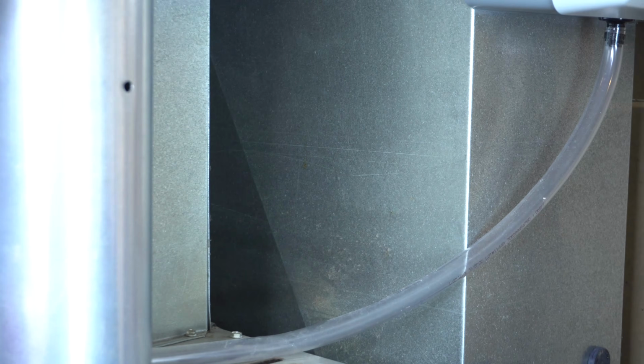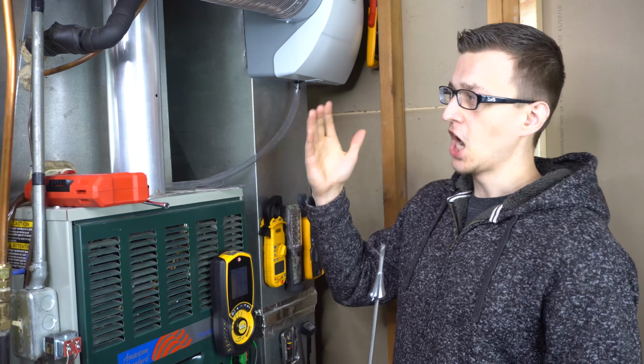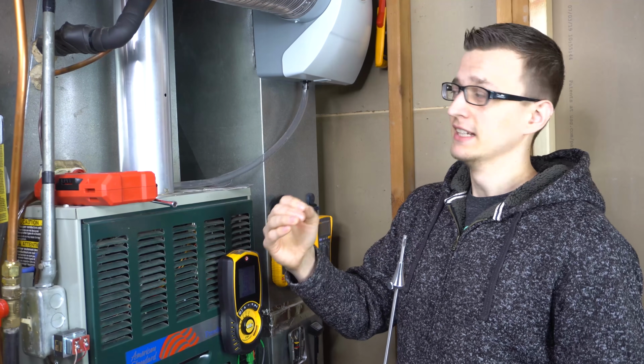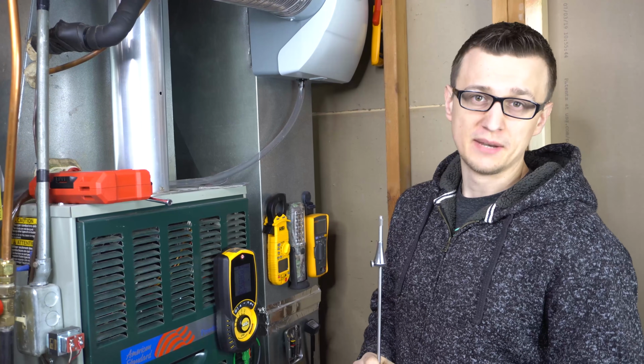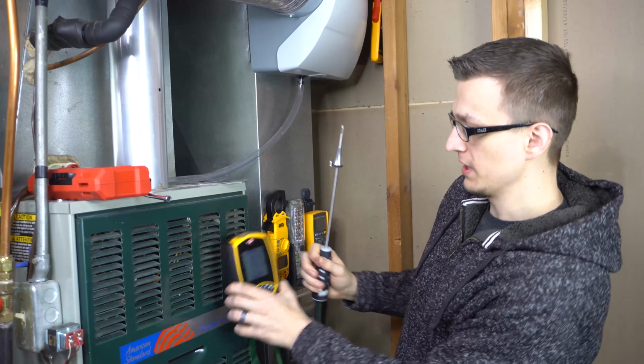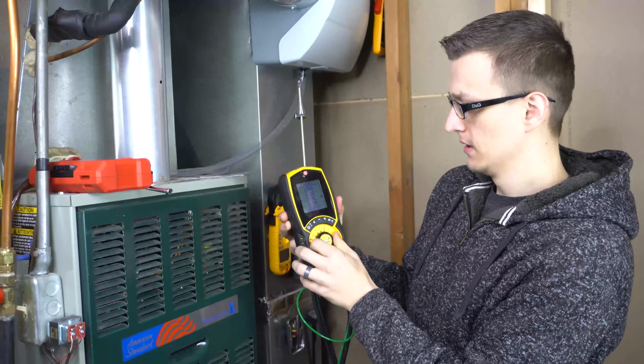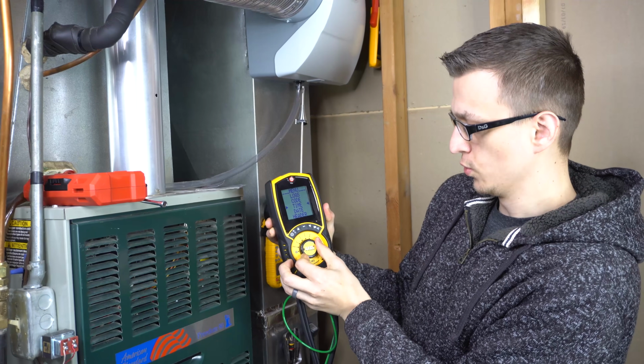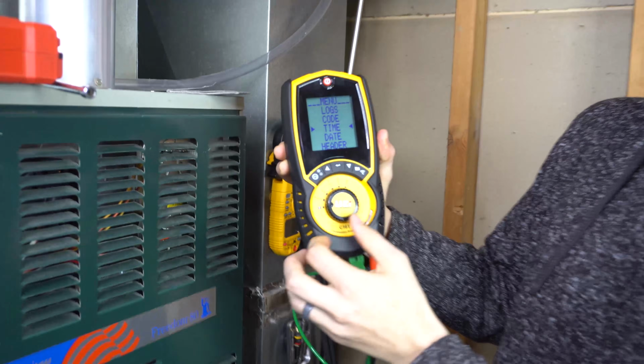So anyways, we have our hole drilled. Let's just turn on our furnace and get some readings. So the furnace has been running for a couple of minutes now, and optimally to get an accurate read, you do want it to run for about 5 to 10 minutes before you get your reading or before you put your probe in. So I'm going to go ahead and turn it to AUX, which is what I usually use, my custom menu.